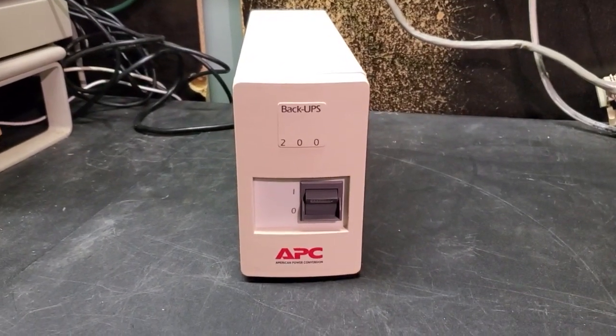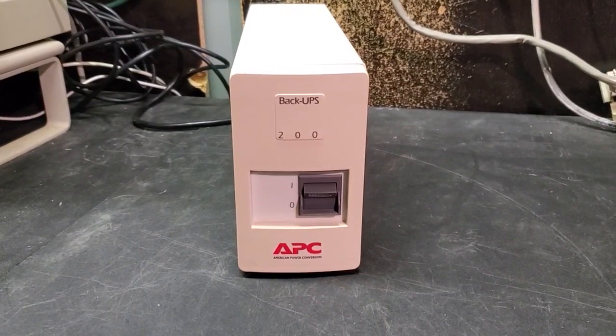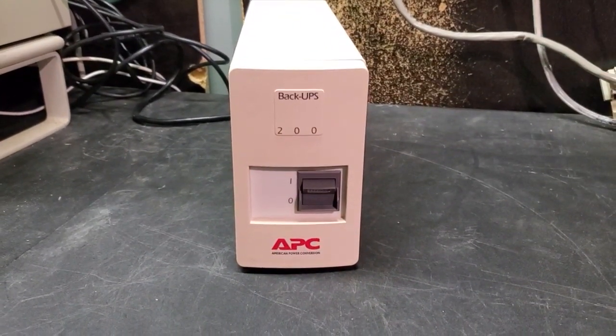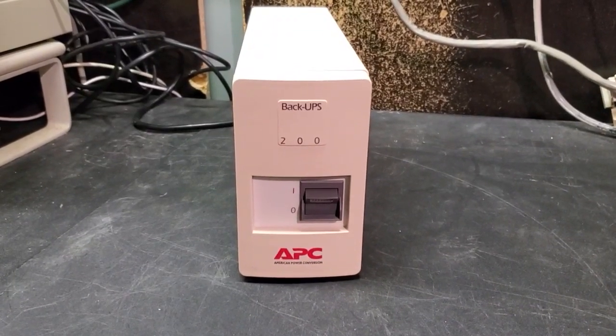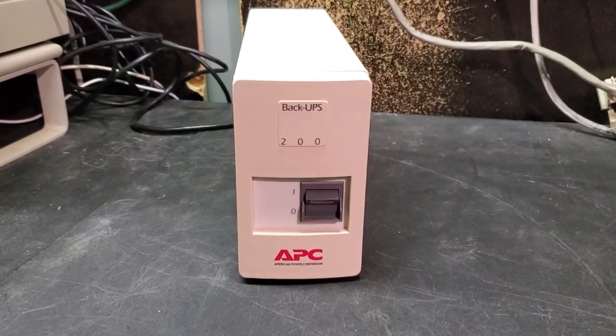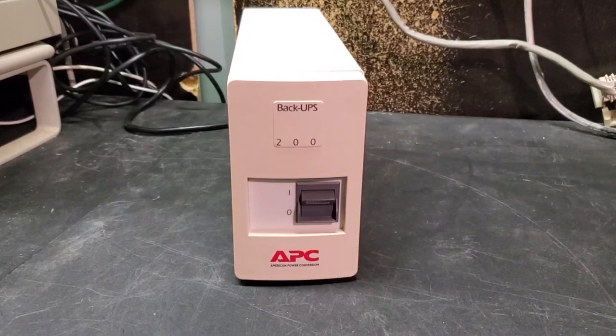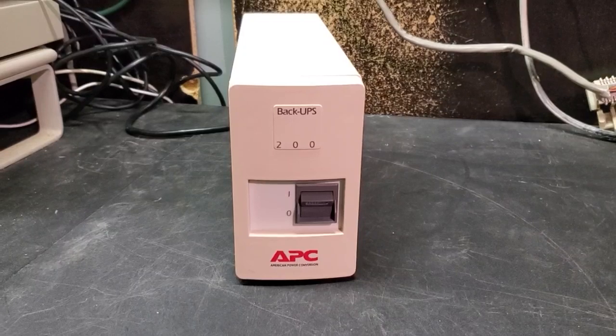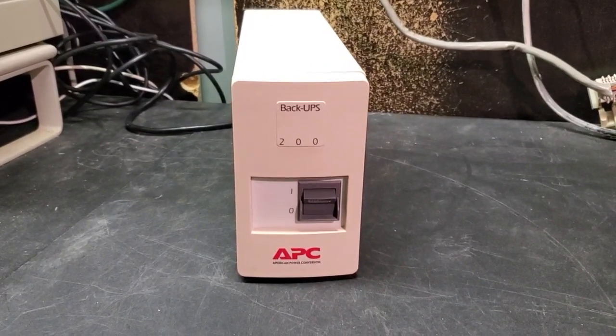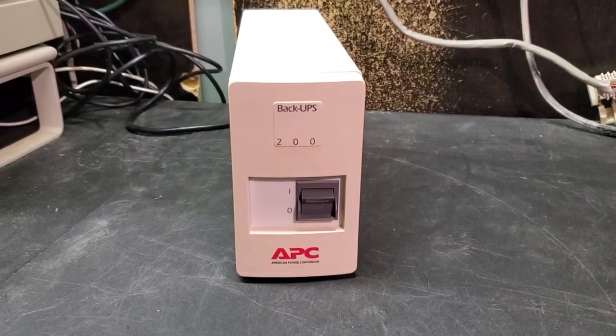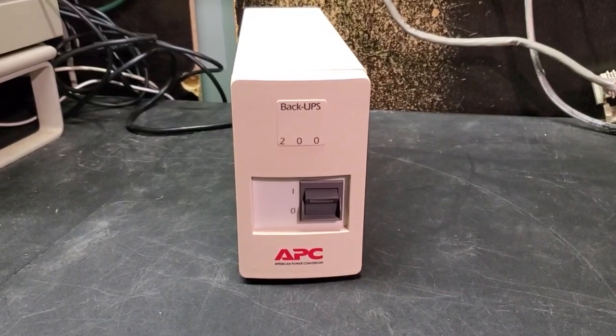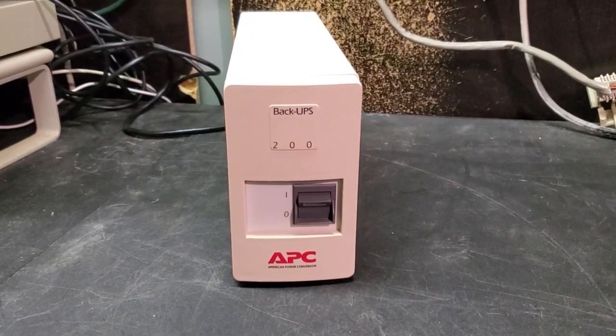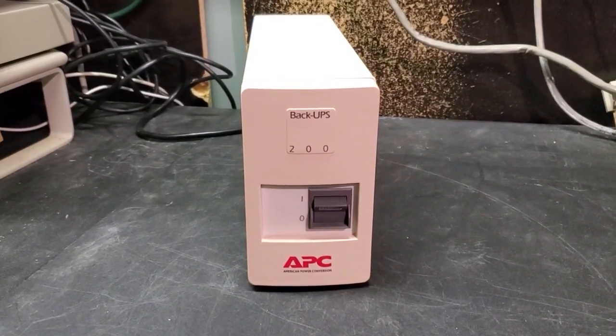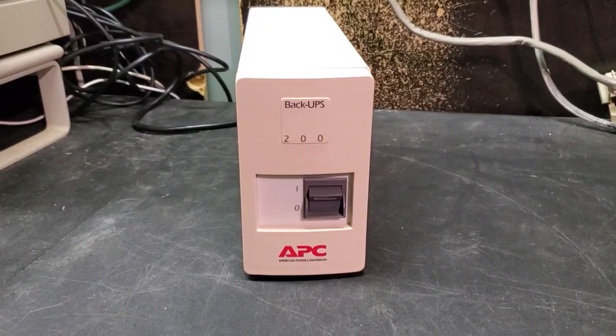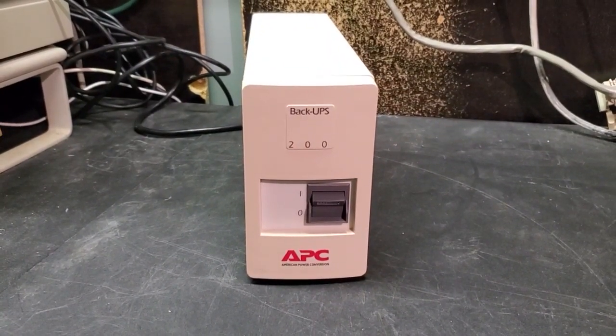Now, if you're up to snuff on your APC product history, you may be saying, well, wait a minute, a couple of years ago APC sold a UPS called the Back-UPS Connect 90, rated for 125 volt amps or 75 watts, and you would be right. APC sold that unit and discontinued it, I think, in 2021 or 22. It was significantly smaller in capacity than this unit. However, I don't consider the Back-UPS Connect 90 a general purpose UPS because, first of all, it only had ungrounded outlets. It did not have grounded outlets.